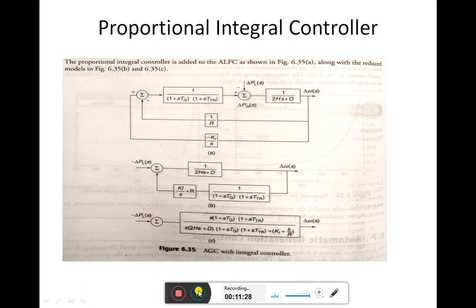In the ALFC loop, there are two parts: primary ALFC and secondary ALFC. The proportional integrator controller shown represents supplementary control, which is much slower than the primary speed control action. It comes into effect only after the primary control has stabilized the system frequency. The primary control acts on all units with speed regulation, whereas AGC adjusts the load reference setting in only a few selected units. The output of these units overrides the effect of composite frequency regulation characteristics of the system, forcing the generation of all units not on AGC to the scheduled values.